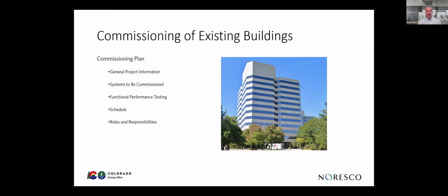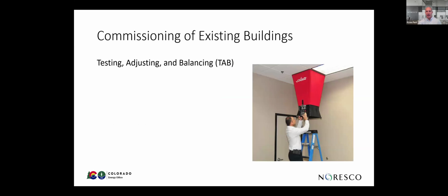So item number 1, commissioning plan. That's what needs to be in it. Your commissioning authority will provide you with that. Second item, TAB, testing, adjusting, and balancing. This is both for air side and water side. And it's a gray area in the code. While this is in the commissioning section, the commissioning authority does not hold that contract, nor does this work. Now, you might find some commissioning authorities that are capable of doing that work, but that is not part of their original contract, usually. So the gray area on this is, it doesn't say what the commissioning authority is supposed to do for TAB.